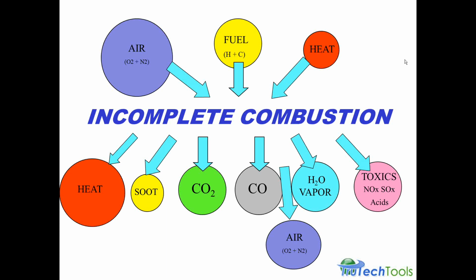Now we move to incomplete combustion, and this is where we're going to introduce the fact that we're using air and fuel and heat. So we still have 3 things on this side, but instead of just oxygen, we now have air with the nitrogen in it, and it's a larger mass. It's a little bit bigger than the little blob we were looking at before. Also, whatever is contained in the air can also move through the combustion system. So in incomplete combustion, we don't go all the way to forming just CO2 and water vapor. We end up stopping partway in the combustion process and forming carbon monoxide.